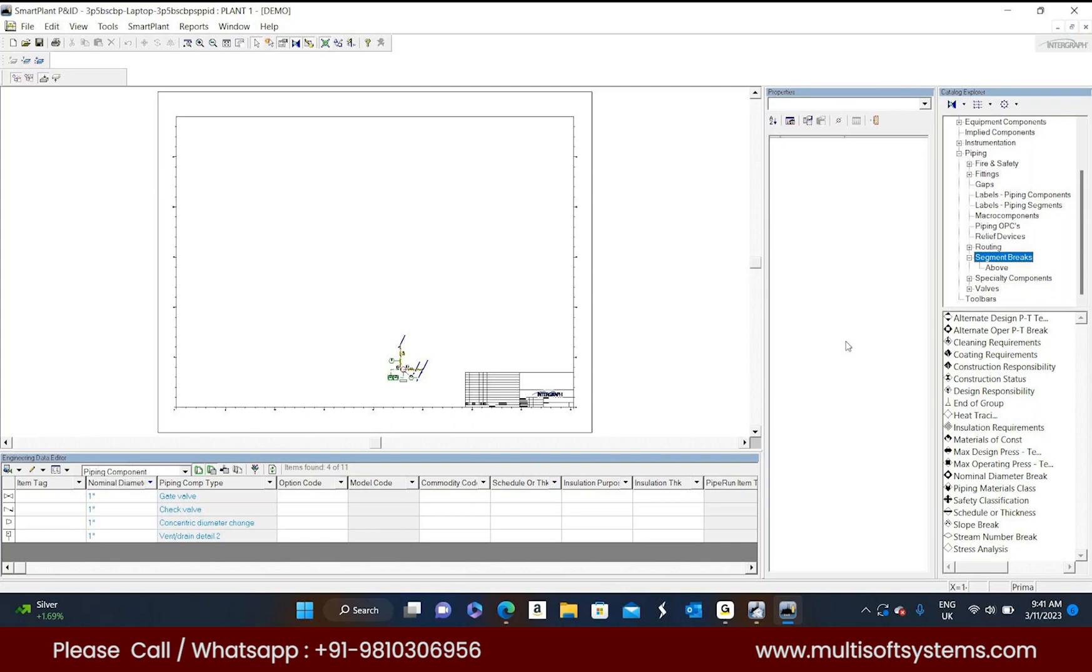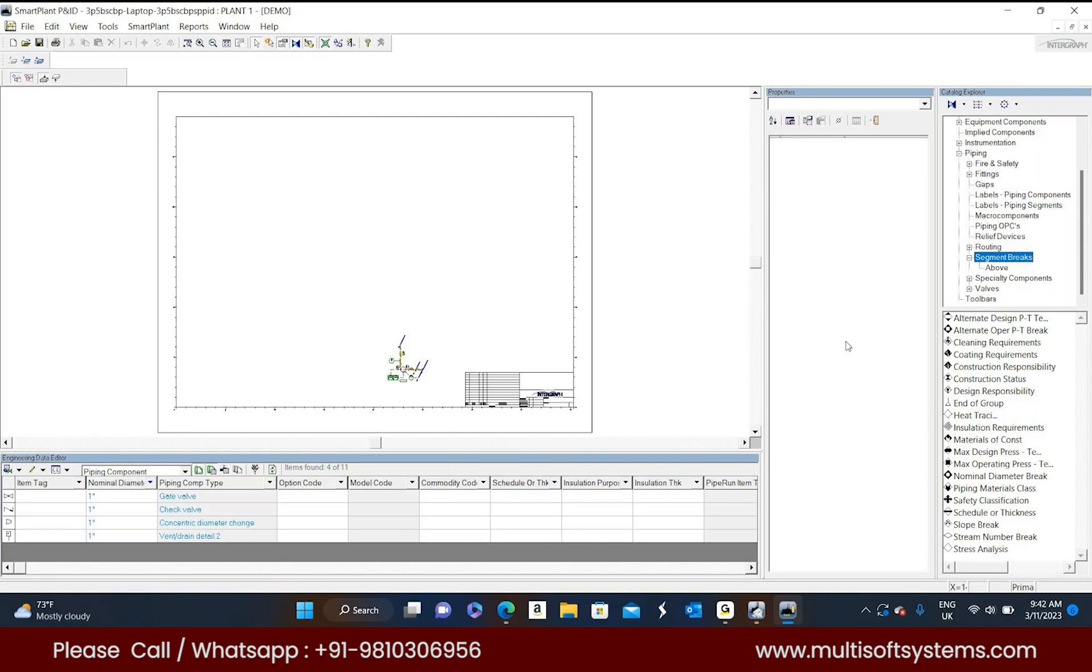Just for example, now there is a pipe run. I am taking the heat tracing symbol break, segment break. For example, it is a six inch line going, reducing into a four inch line. Only the four inch line needs heat tracing. So you have to place the break at the - should I place the break on the upstream of the reducer or the downstream of the reducer? Or it is defined by the process engineer. Actually in P&ID, all the properties will be defined by the process engineer only. The user won't define anything. Based on the process engineer, he will draft the P&ID.